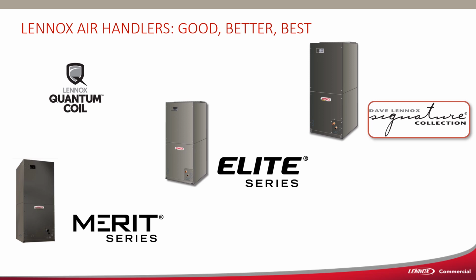On the air handlers, we have our good, better, best to match the condensing units. Our good is the CBA 25, our better is the CBA 27, and our best is the CBA 38. The CBA 38 and the 27 both have variable speed fans. But all of these products have our new Quantum coil in them. This is an aluminum tube, aluminum fin coil. It is not a microchannel, it's aluminum tube and aluminum fin, and the aluminum alloy it's made of was designed and invented by us at Lennox. And it is completely immune to formicary corrosion.